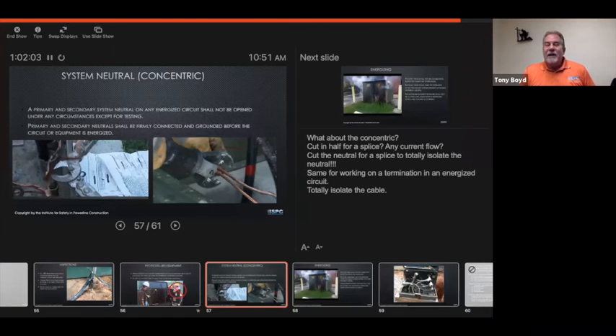So if we have 3 phases, whatever the difference in amperage on those 3 phases is, and I don't know any 3-phase system anywhere that is totally balanced in amperage, so there's going to be some difference. Whatever that difference is, that amperage or return current is going back to the source on the system neutral. And then a single phase system neutral is just returning the current back to the source. So our system neutrals are always containing current. That's why we ground them at every pole, or every so often on every pole, every piece of equipment or whatever. But that's why we ground.